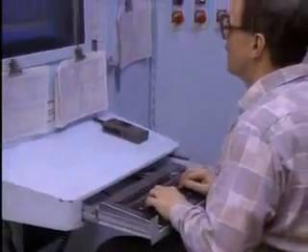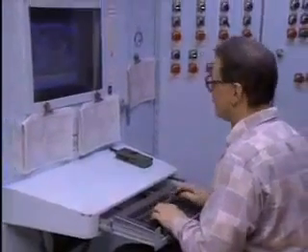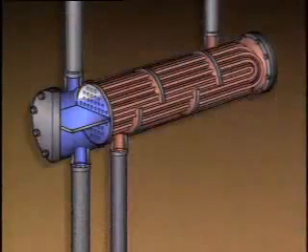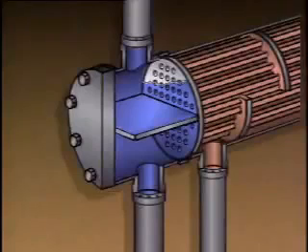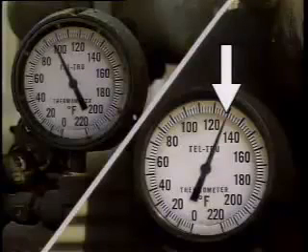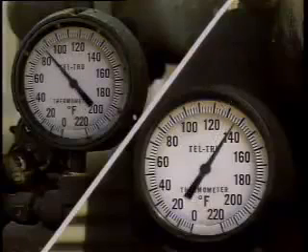No matter how air or other gases get trapped inside a heat exchanger, they can cause it to become air bound or vapor bound. There are several symptoms to indicate this. For example, when trapped gas blocks flow to some of the tubes, the outlet temperatures of the two fluids may change. This is because the gas is restricting flow into the tubes, and the restricted flow causes less heat transfer surface area to be available. The decrease in heat transfer surface area will cause the outlet temperature of the process fluid to increase, since less heat will be removed from the fluid.